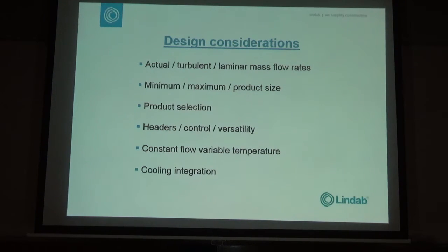I know a lot of the perceived ideas at the moment is to vary the flow with an inverter on the pump and things like that, but really a radiant panel works better with a constant flow rate and vary the temperature of the water to the panel, because that's the panel works better on that basis. And then the panel is always on because it's always warm.